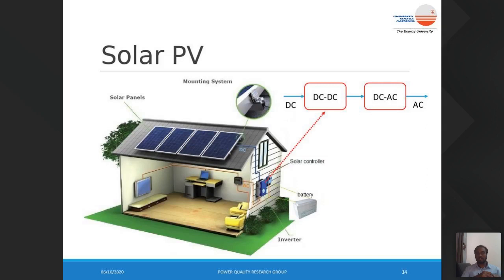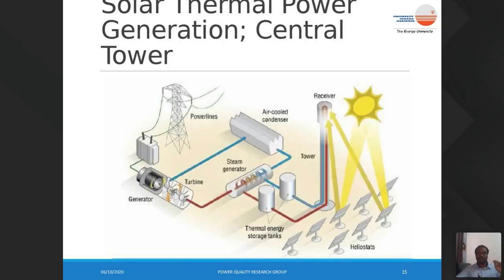It's because suppose the line voltage is say 400 volts, you need to have a DC link voltage at least 1.7 times that of the line voltage. So you need at least 700 volts at the DC bus to invert it to 400 volts AC. So that's one of the main reasons we usually go for a two-stage conversion process.